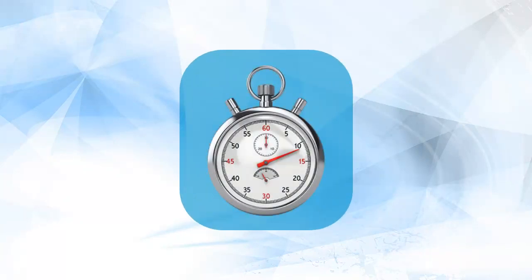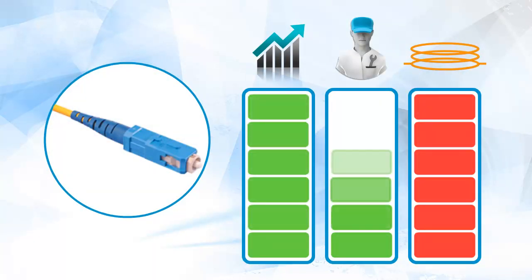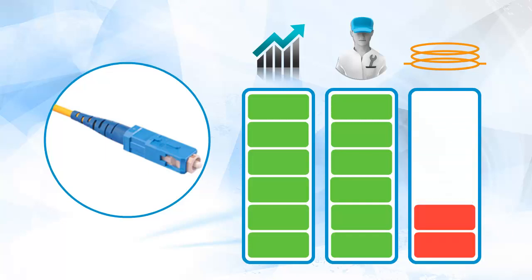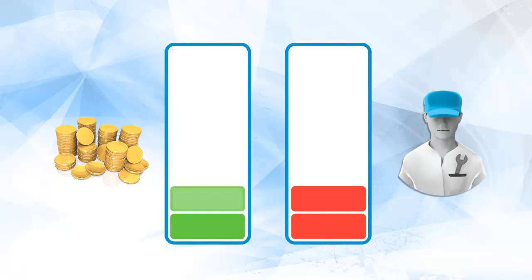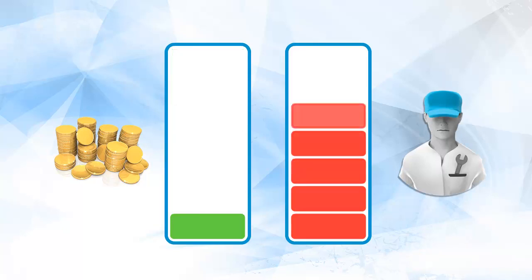The accessibility and thus the amount of time required to reconfigure the network is optimal in a system that maintains a continuous non-coiled or twisted routing of fibers. As single-mode connectors become more reliable and easier to install in the field, some of the need for slack storage will disappear. It is also true, however, that terminating the connectors in the field while reducing the initial ODF purchase price will increase the installation cost and time.